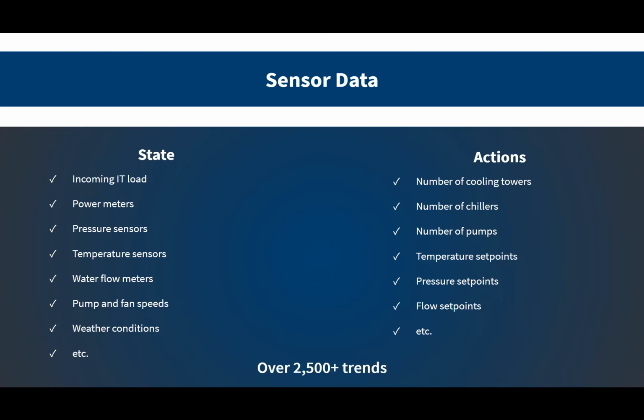On the action side, these are the things our AI system is actually controlling. You've got decisions like which cooling towers, chillers, and pumps should we be running. What are the temperature set points associated with these various pieces of equipment? What are the flow rates? What percent pump speed should we run at? What's the RPM? What are the flow set points, etc.